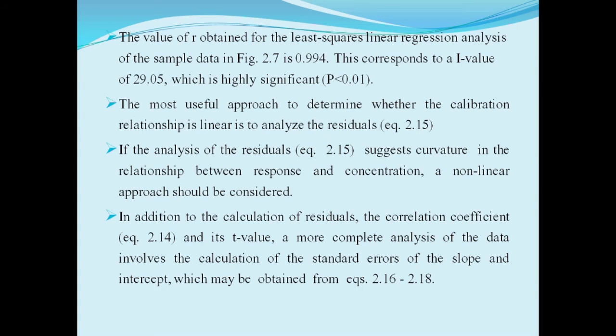Although the value of the correlation coefficient R is readily obtained, it should not be relied on to establish the linearity of the calibration data per se, because calibration data that have a high degree of curvature can give a high value of R greater than 0.99 and a statistically significant value of t.